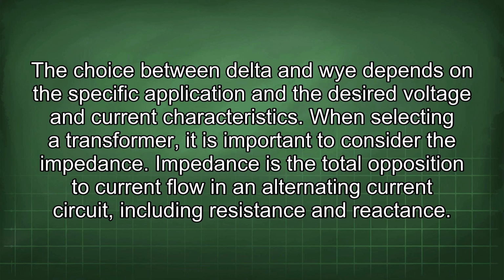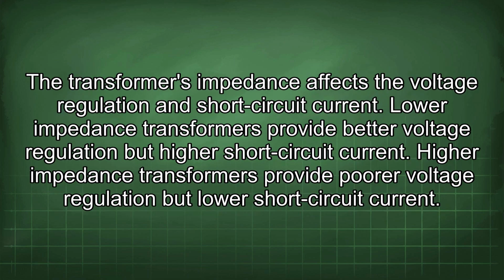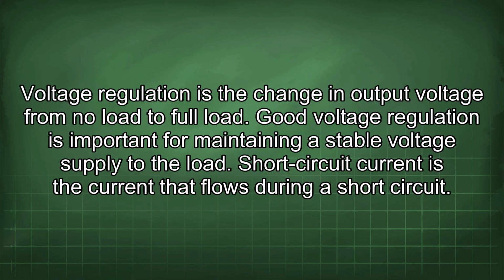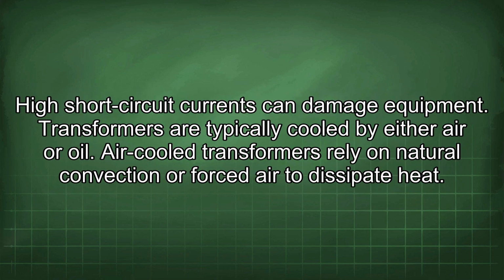When selecting a transformer, it is important to consider the impedance. Impedance is the total opposition to current flow in an alternating current circuit, including resistance and reactance. The transformer's impedance affects the voltage regulation and short-circuit current. Lower impedance transformers provide better voltage regulation but higher short-circuit current. Higher impedance transformers provide poorer voltage regulation but lower short-circuit current. Voltage regulation is the change in output voltage from no load to full load. Good voltage regulation is important for maintaining a stable voltage supply to the load. Short-circuit current is the current that flows during a short circuit. High short-circuit currents can damage equipment.